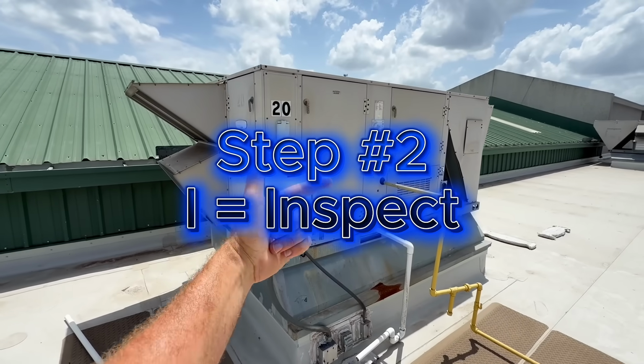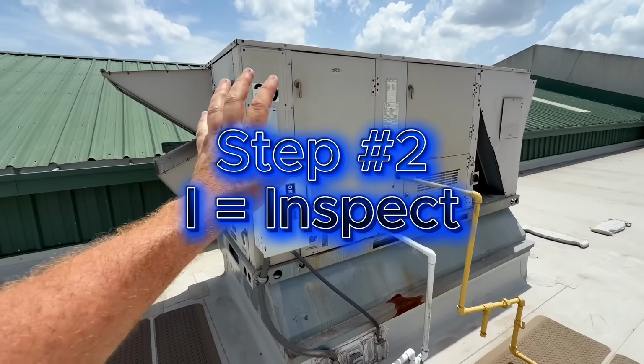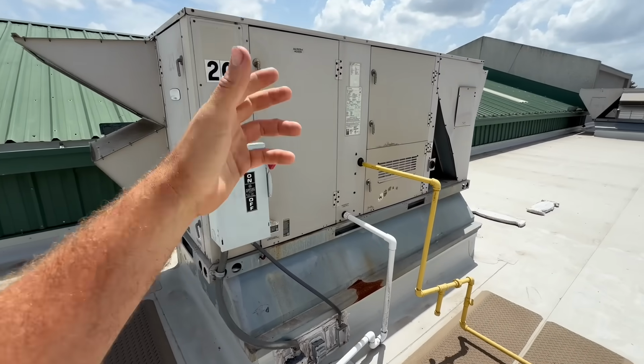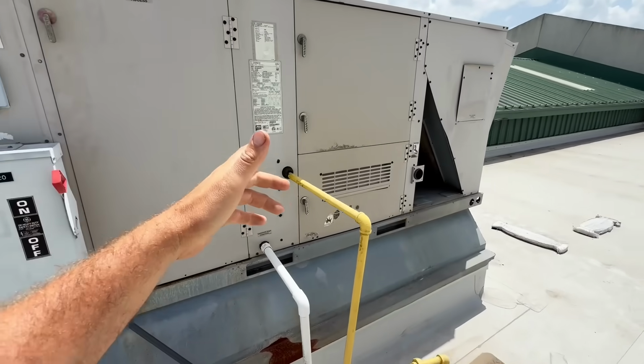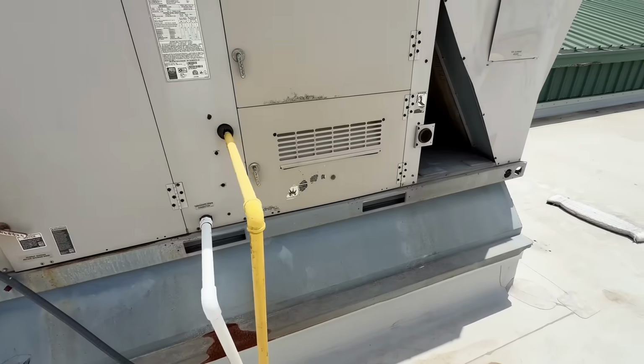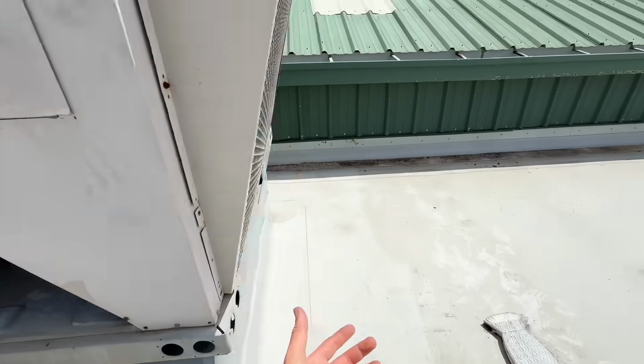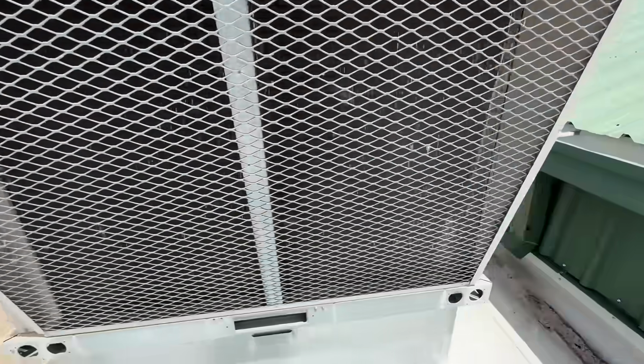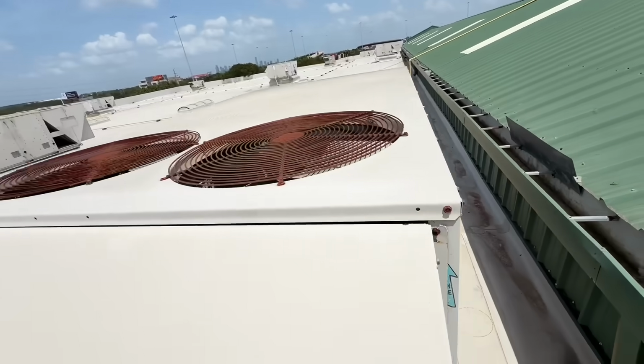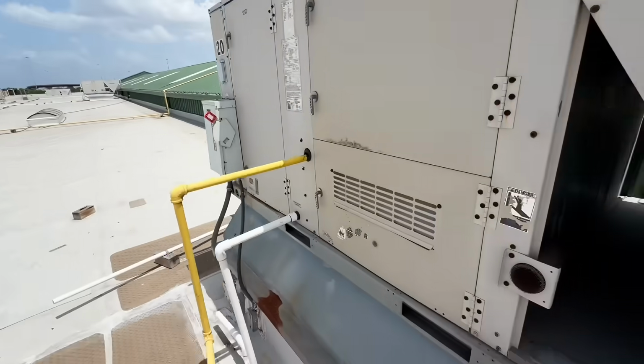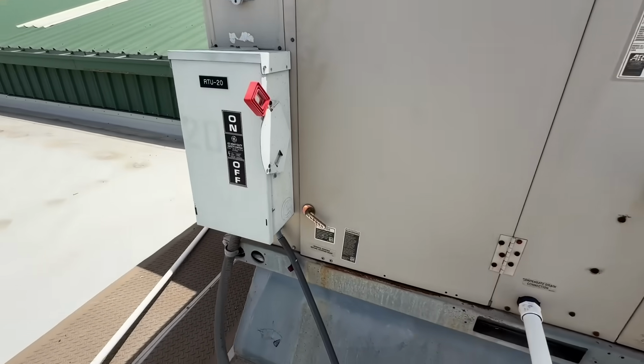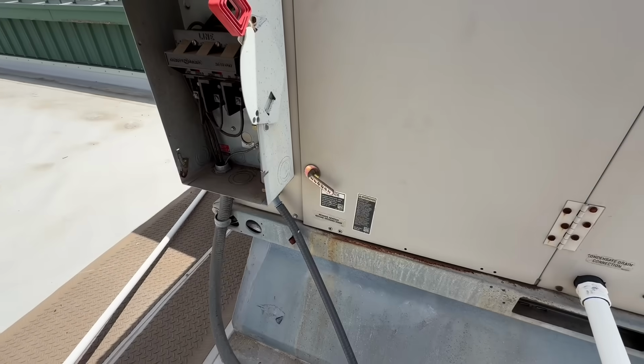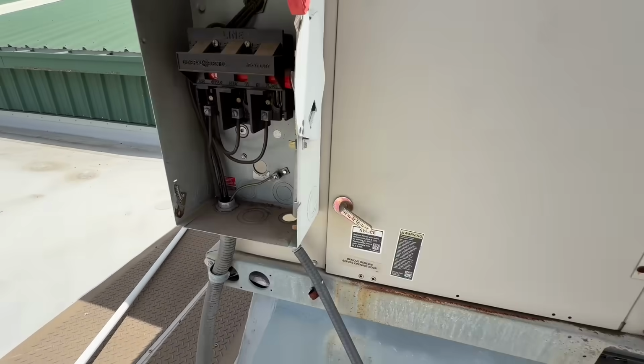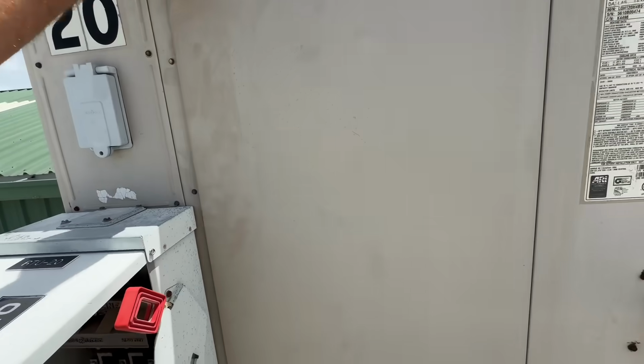Step number 2 is inspect. So you do a visual inspection of the unit. You don't really touch anything, you just look around. Obviously, we already found that the breaker is off, but just confirming, I don't see anything majorly going on over here. I'm just inspecting. It's obviously not running. I see that this is slightly open, which makes me believe somebody else has been looking at this before. It is not fused. We can open over here.